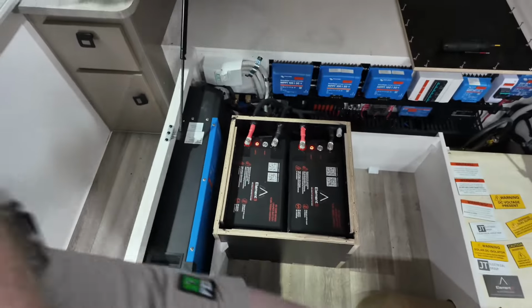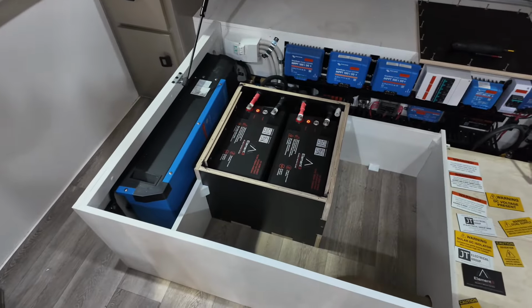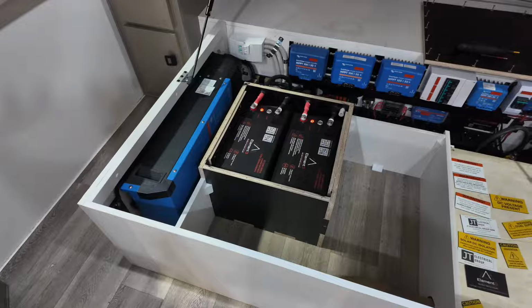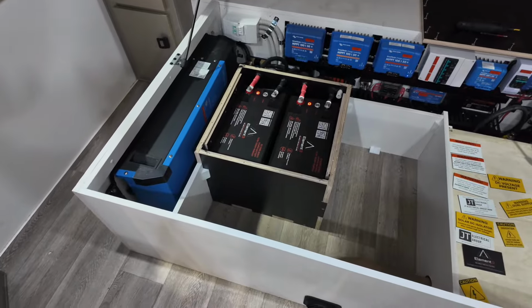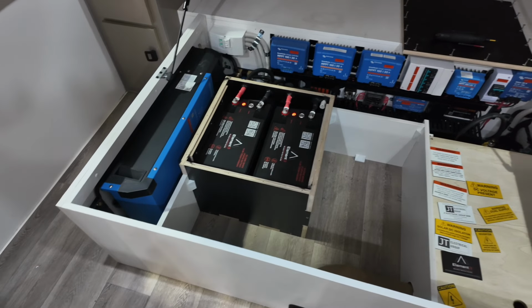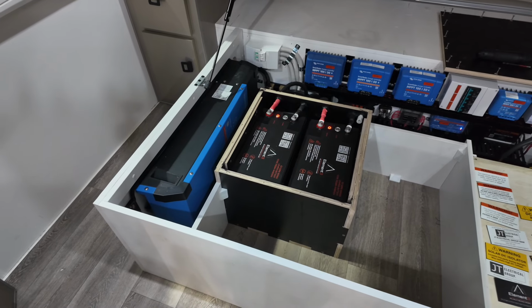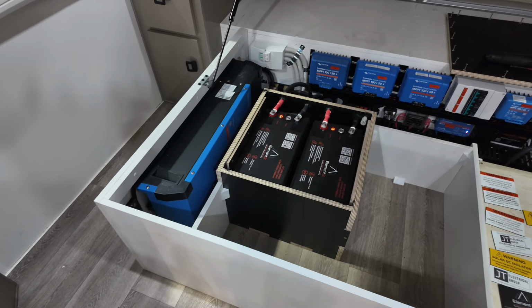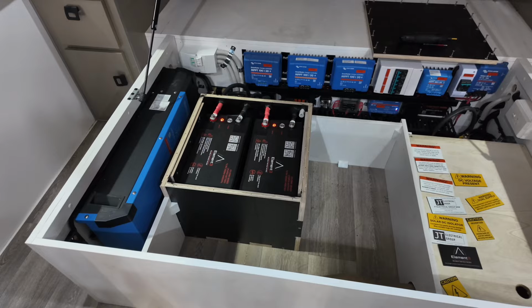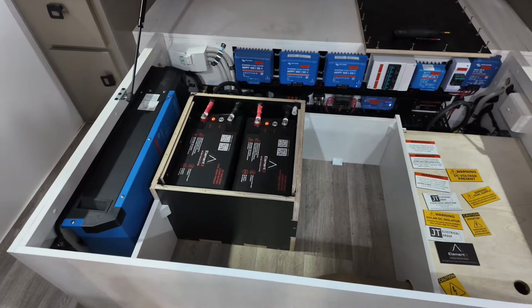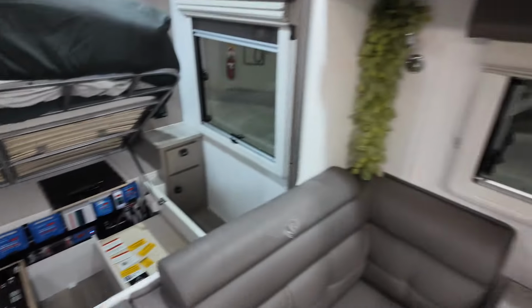5kVA inverter, you've got 2 times 70 mils. Yes, people are going to say, oh, I should have done 24 volt on a 5kVA setup, less cable between the battery - it's like half a meter, mate. It's okay, relax, it's not going to make the world's biggest difference, a couple extra bucks in cable here and there. Because with a 24 volt system, you're buying the converter to step it down to 12 volt anyway, since all these lights and whatnot are 12 volt only, not dual input.